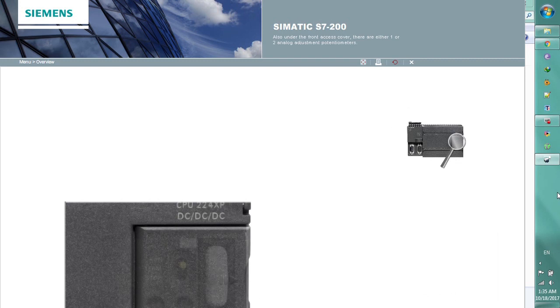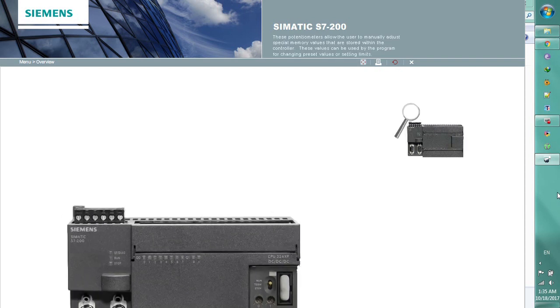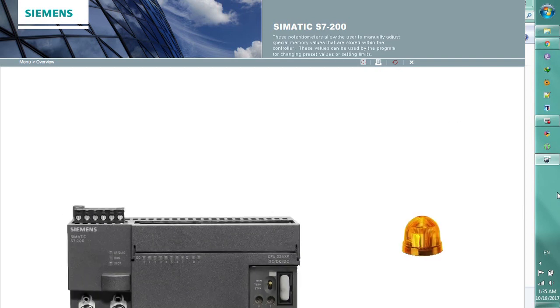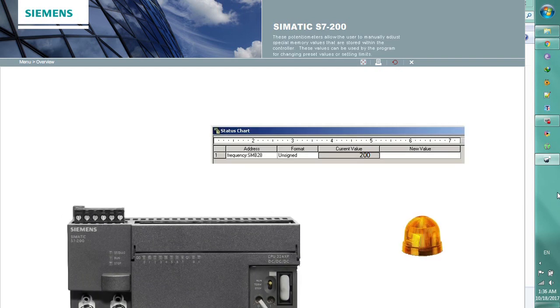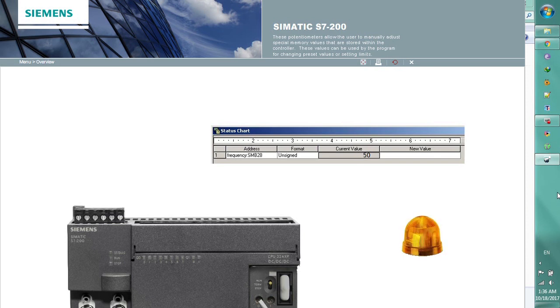Also under the front access cover, there are either one or two analog adjustment potentiometers. These potentiometers allow the user to manually adjust special memory values that are stored within the controller.